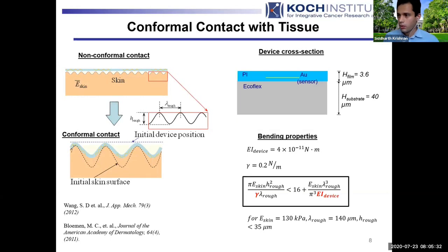When the device just sits on skin, you're going to have motion artifacts, low quality contact, all kinds of noise, and it'll probably move when the person moves. What you really want is something that looks more like the bottom left cartoon, where the devices are truly conformal to the textures and grooves of the skin surface, or indeed any biological tissue. There are certain engineering knobs you can turn to accomplish this — most prominently, the bending stiffness, which is the product of the Young's modulus and the second area moment. It scales most dramatically with device thickness, and you can also tune the surface energy. Long story short, you can make devices sufficiently soft and thin, and tune the surface energy to accomplish conformal contact.